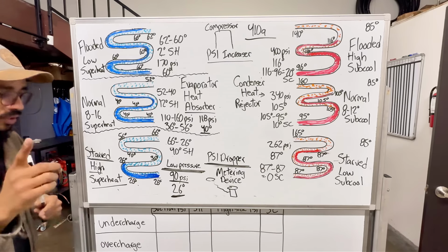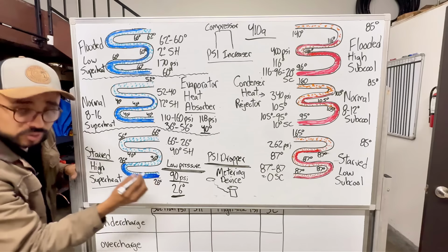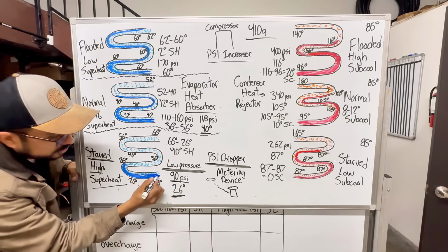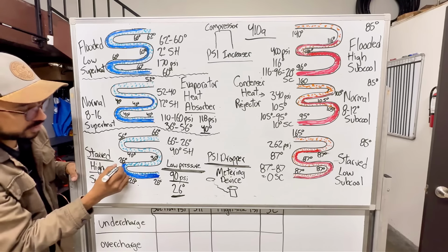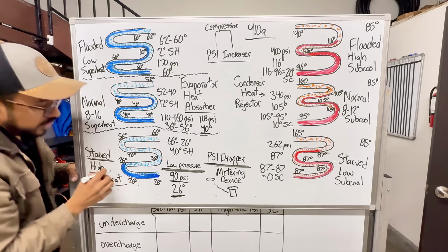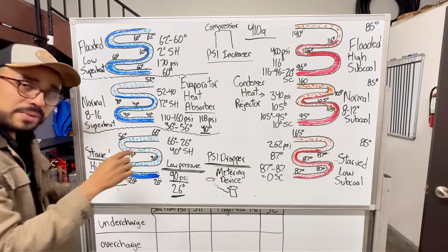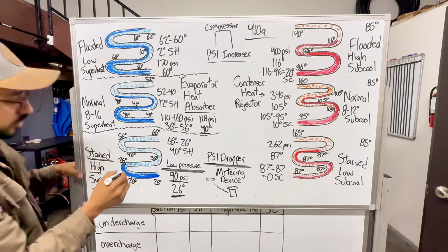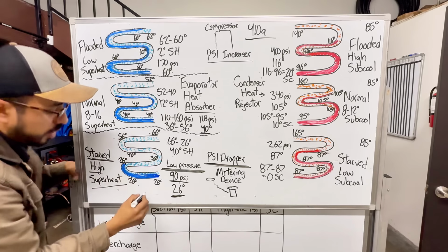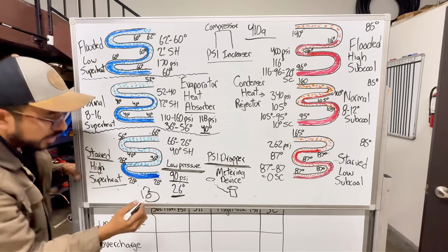But look at the superheat. We already talked about how latent heat, saturated, as long as it's saturated, temperature stays the same: 26, 26, 26. But once the last molecule of liquid boils off and you only have vapor, now it gains sensible heat, now it gains temperature: 36, 46, 56, 66. Remember, what's throwing all that hot air is your return.